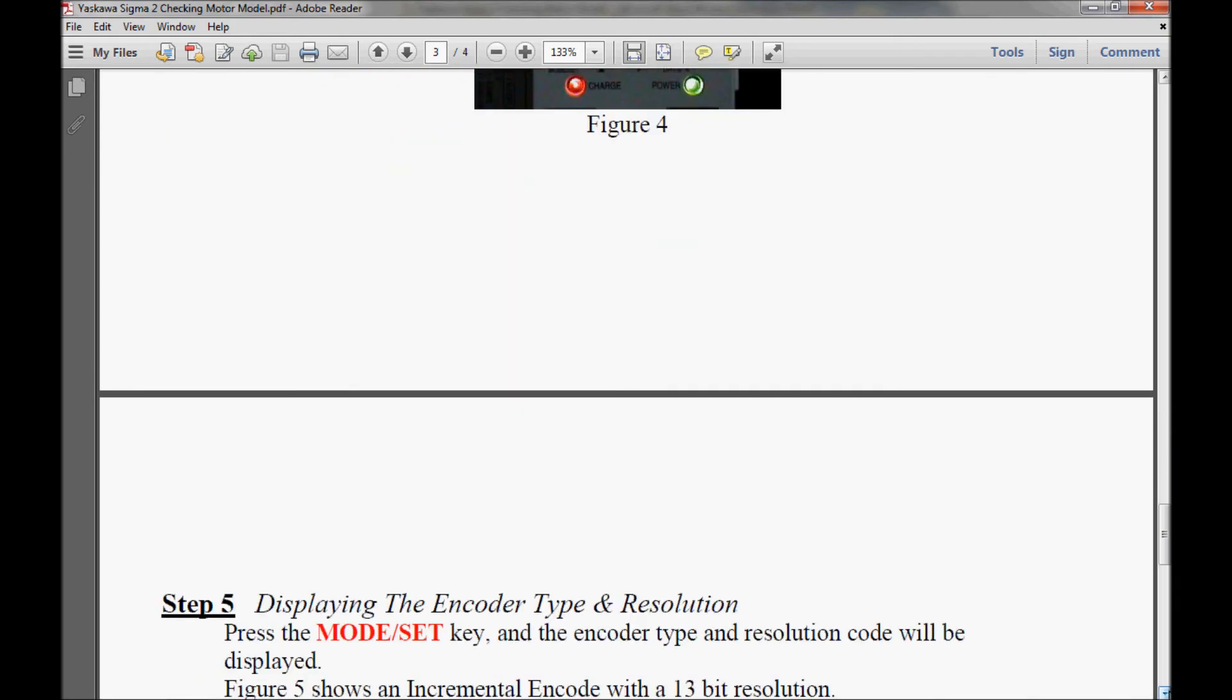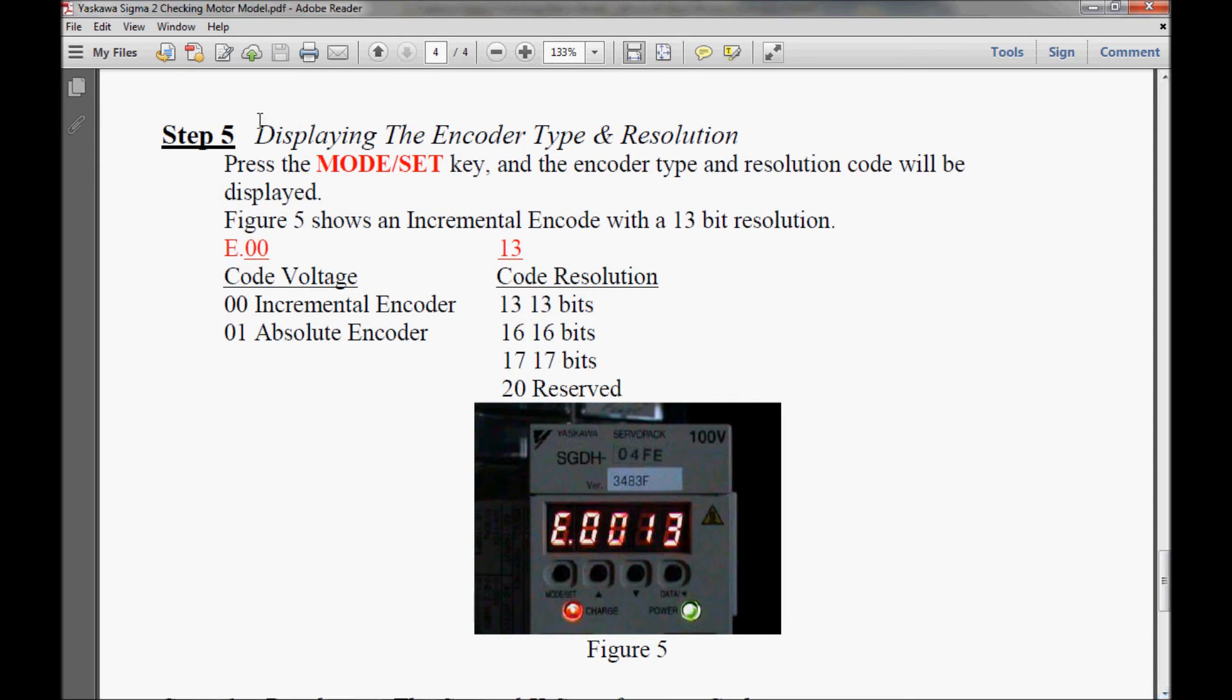And here in step 5, I am displaying the encoder type, also the resolution. It's similar to step 3, where you have E.00. The 0, 0 would be the code for the type of encoder it is. And in this case, it is an incremental encoder. And then the 1, 3 is the code resolution, which is a 13-bit encoder.